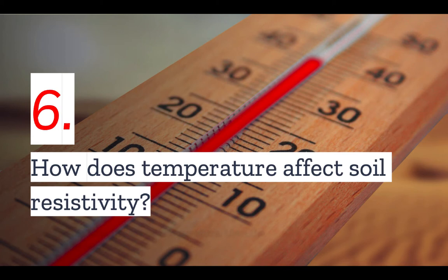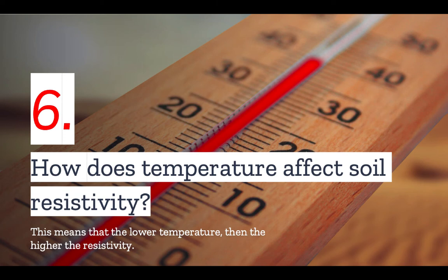Number six: how does temperature affect soil resistivity? The temperature coefficient for resistivity is negative. This means that the lower the temperature, the higher the resistivity. This is particularly important if you are in a cold climate, because lower temperatures can affect your grounding systems.